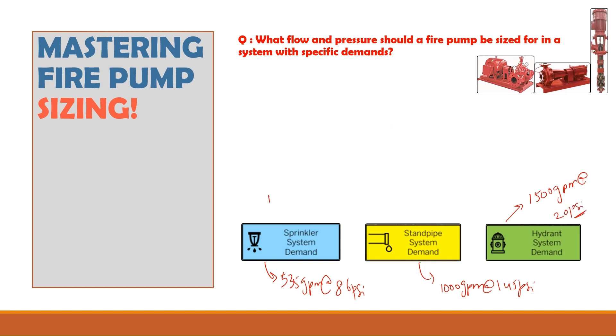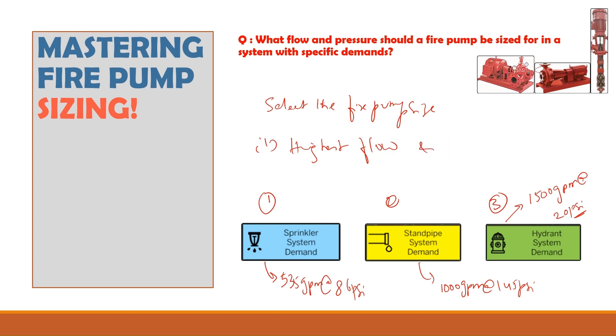Based on these three values, we need to select the fire pump based on the highest flow and highest pressure. It is very simple. We select the fire pump as 1500 gpm at 145 psi.